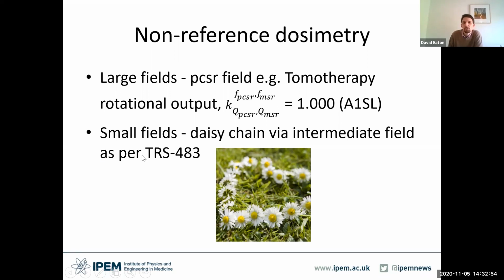So non-reference dosimetry might include large fields. One area I haven't really touched on is the plan class specific reference field. So you may have a machine specific reference field with, for example, a different field size or a different spectrum. But you may also have a machine that delivers radiation in a non-reference way. For example, tomotherapy units are typically calibrated to a rotational output, not a static output. So in that case, you will have another factor.